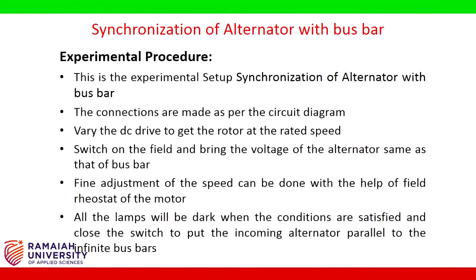Vary the DC drive to get the rotor at the rated speed. Switch on the field and bring the voltage of the alternator same as that of the bus bar. Fine adjustment of the speed can be done with the help of field rheostat of the motor. All the lamps will be dark when the conditions are satisfied. And close the switch to put the incoming alternator parallel to the infinite bus bars.